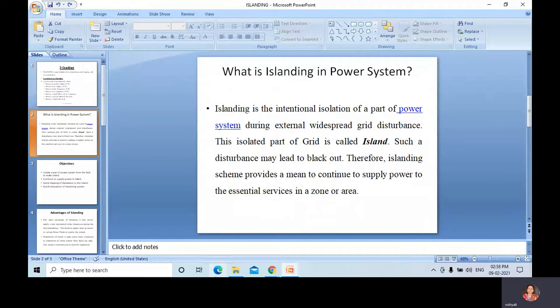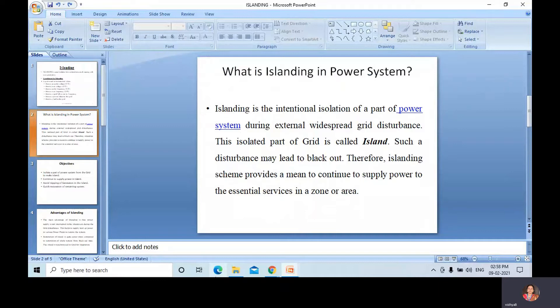What is islanding in a power system? Islanding is the intentional isolation of a part of a power system due to an external widespread grid disturbance. This isolated part of a grid is called an island. Such a disturbance may lead to a blackout if we do not isolate that part. So we go for the islanding scheme to continue supplying power to essential services in a zone or area.